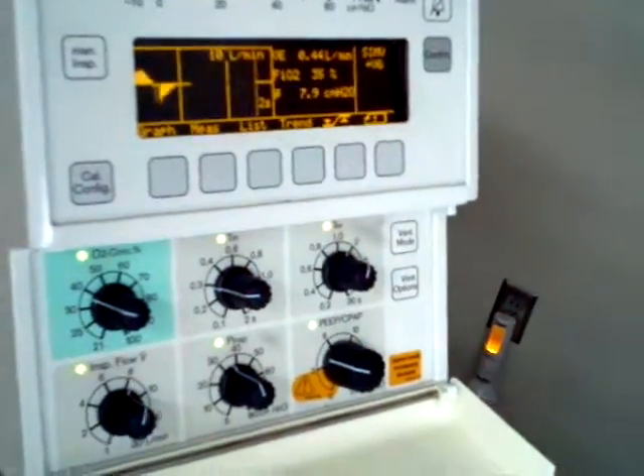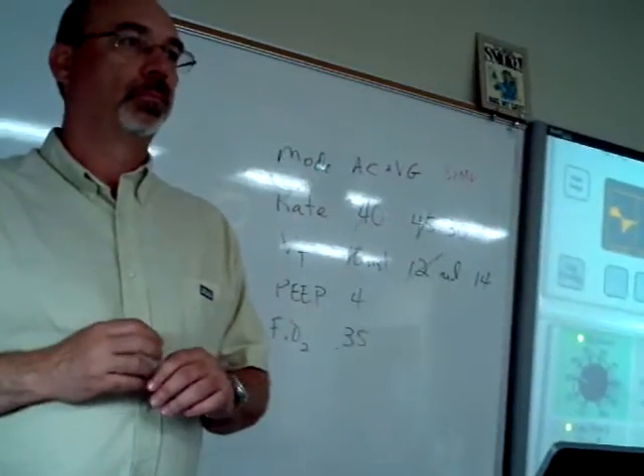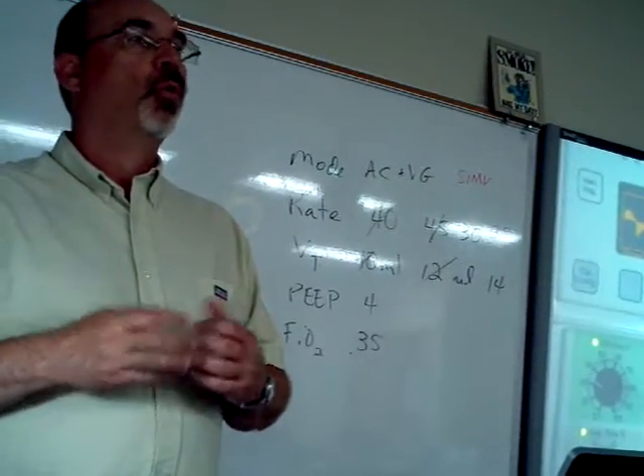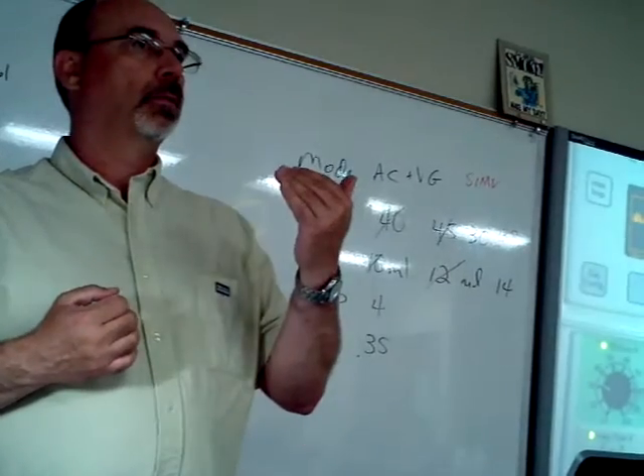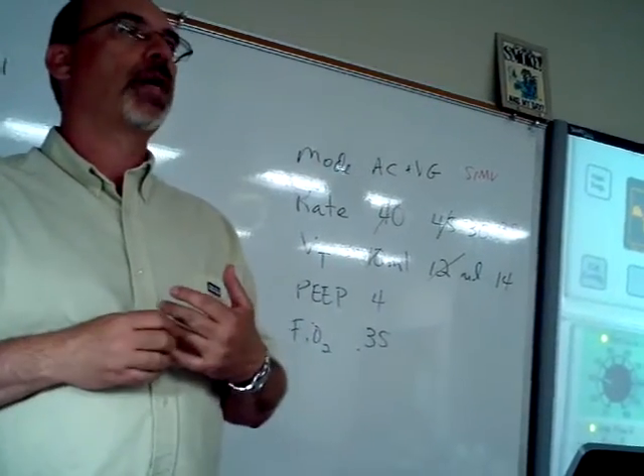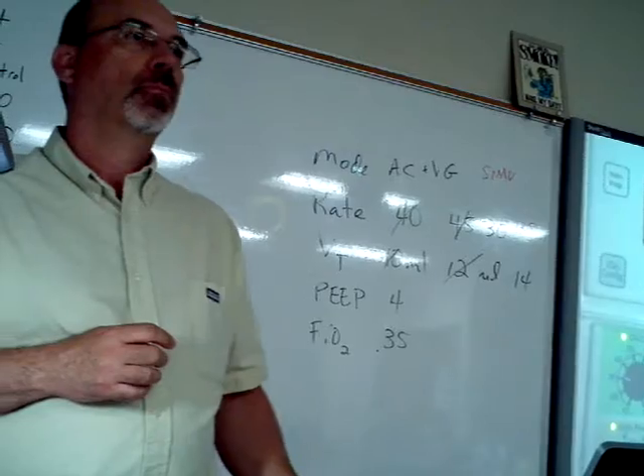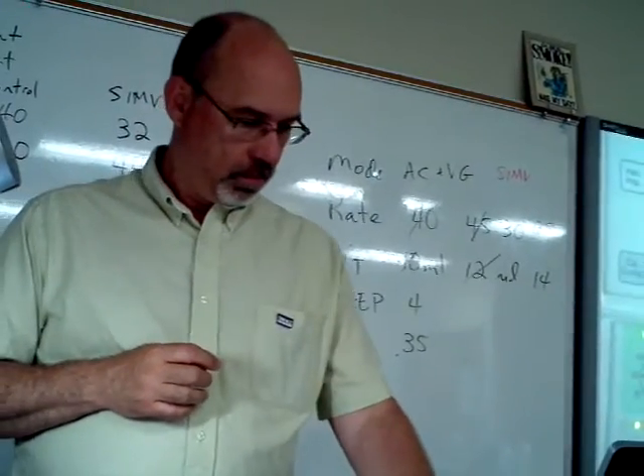When you start changing and you go and set your alarms, does the vent pretty much calculate the setting for you, the plus or minus? It will calculate the alarms, yes, it does plus or minus 30%. Okay. Yeah, it does that for you.